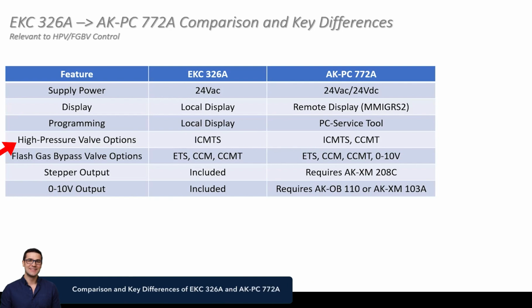Valves, really, the pack controller can cover anything the EKC could and more. So on the high pressure side, it can drive the ICMTS still, or it could drive a CCMT if that was the valve we were using on the high pressure side. And then on the flash gas side, similar, anything we need to cover for the valve type there, we can do that.